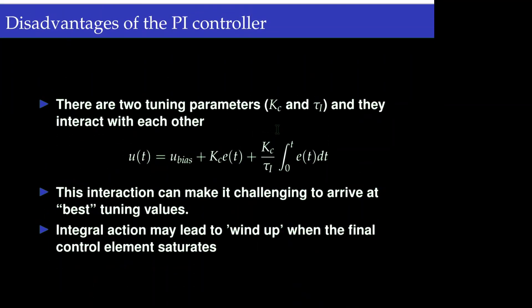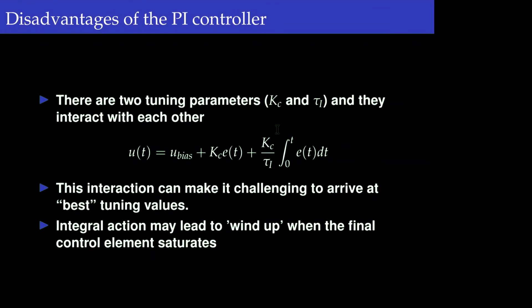There is another issue: we now have two parameters, Kc and tau_i, and finding the best tuning values for both is a challenge. Another problem with the integral action is what is called integral windup, which is caused by the saturation of the final control element.